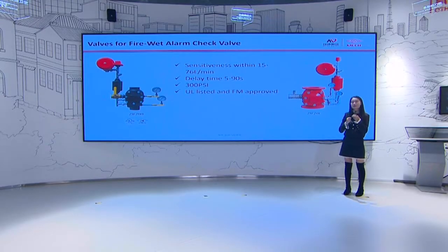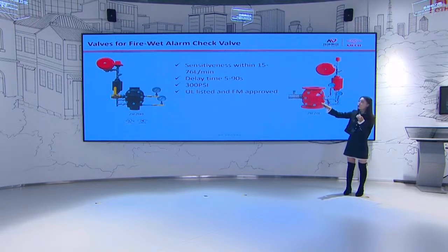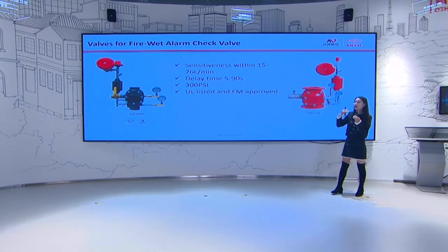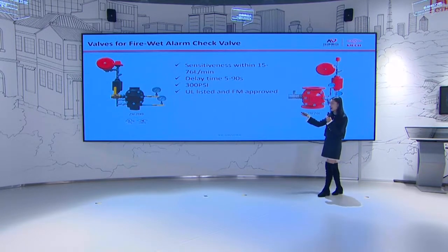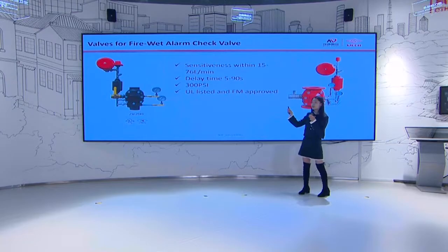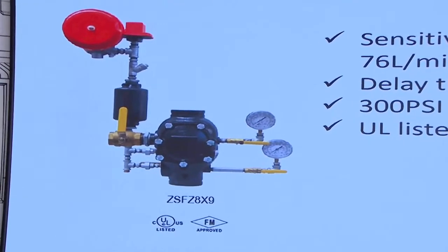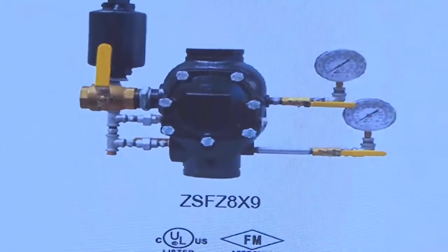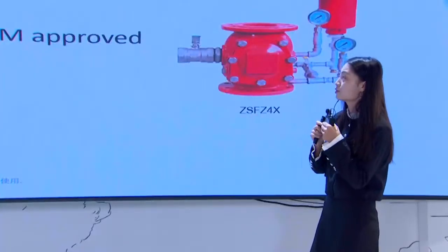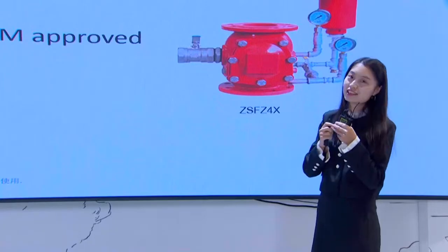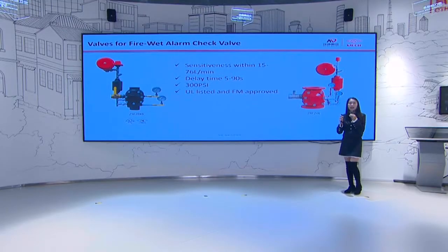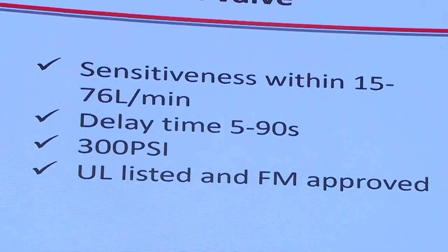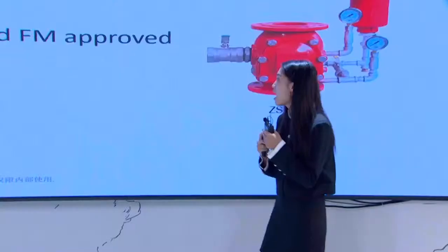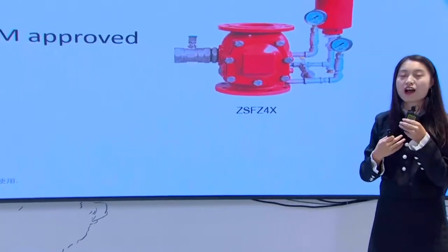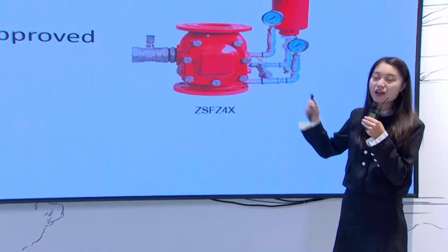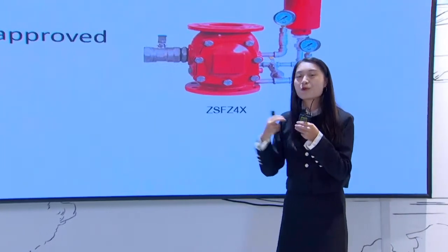Here is our big highlight, our wet alarm check valve. We are happy to say this product has already got UL listed and FM approved. The flow rate is 15 to 76 liters per minute, the delay time is 5 to 90 seconds, and the working pressure is rated at 300 psi. At the same time, we are working on certification for the flange type, and when we get it, we will let you know.